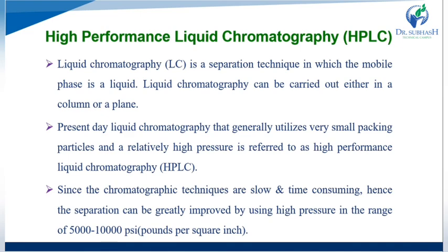Since chromatographic techniques are slow and time consuming, separation can be greatly improved by using high pressure in the range of 5000 to 10,000 psi, that is pounds per square inch.